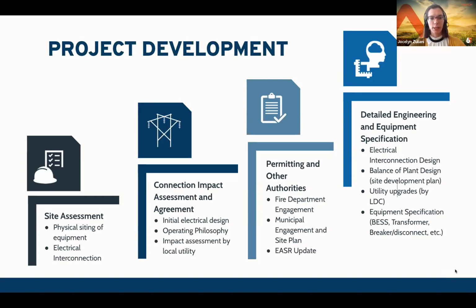After we've determined how we're going to connect the system, we go through the connection impact assessment. This involves developing the initial interconnection design, an operating philosophy, and engaging with the local utility to complete an impact assessment. Depending on your jurisdiction, the operating philosophy is often key, so the utility can understand how you're going to use the battery and study it appropriately in their system impact assessment.